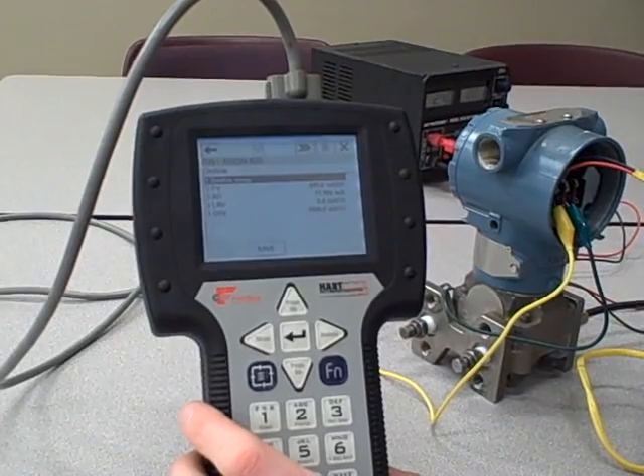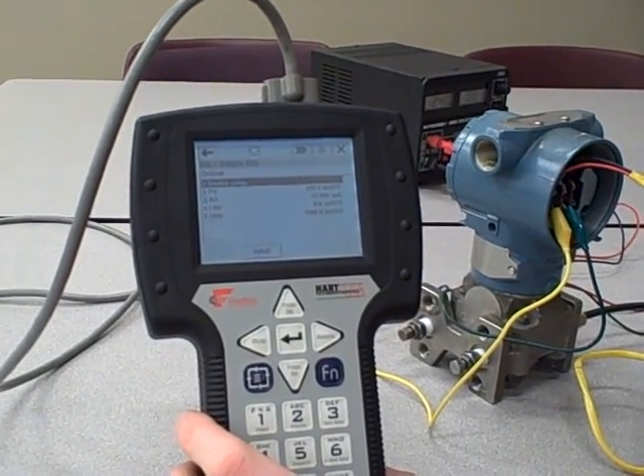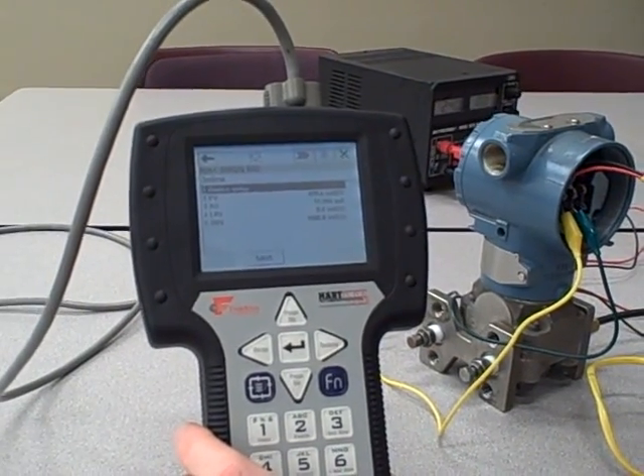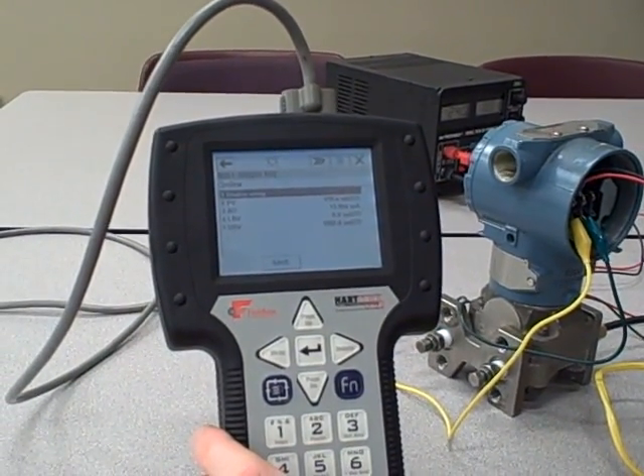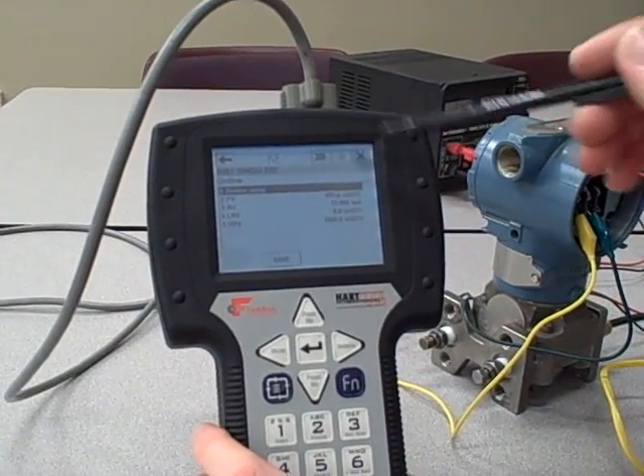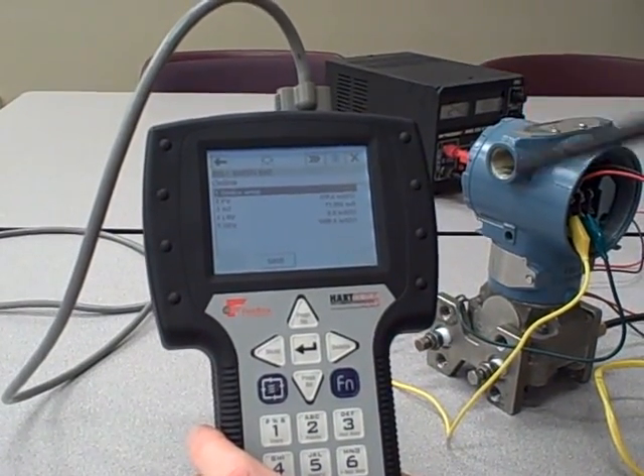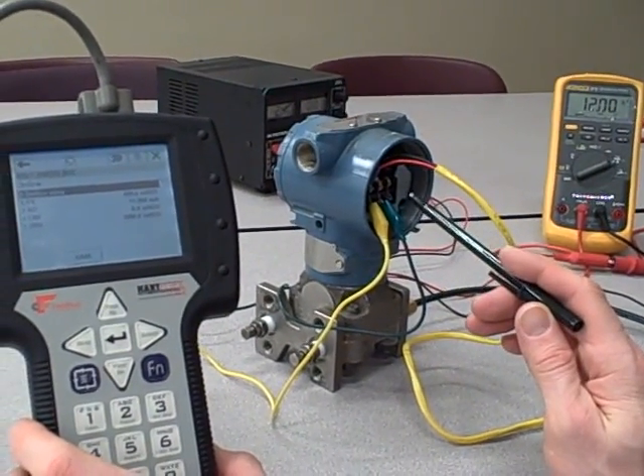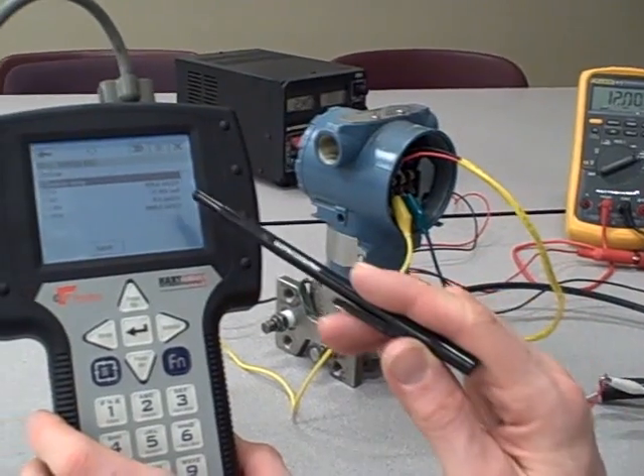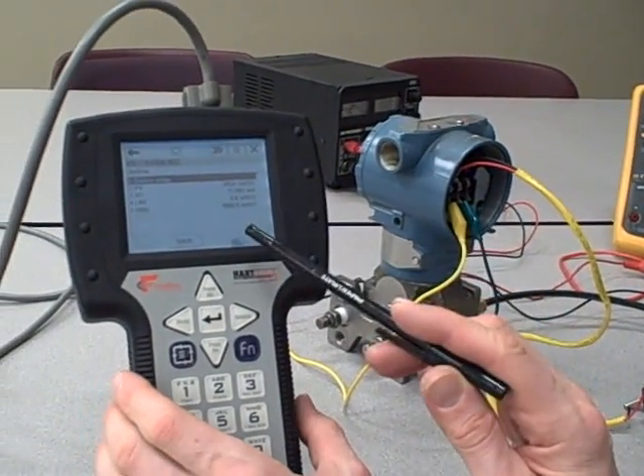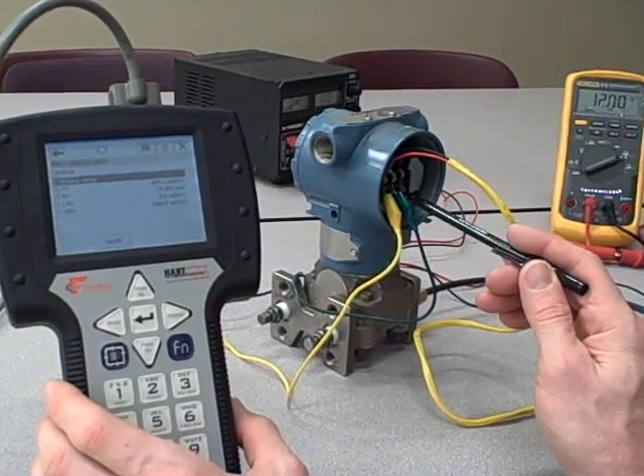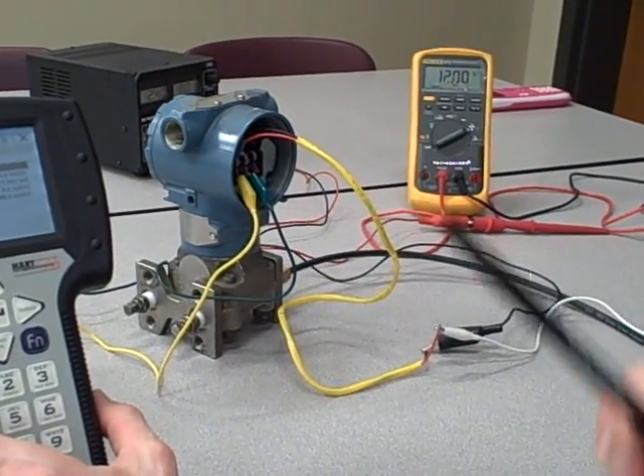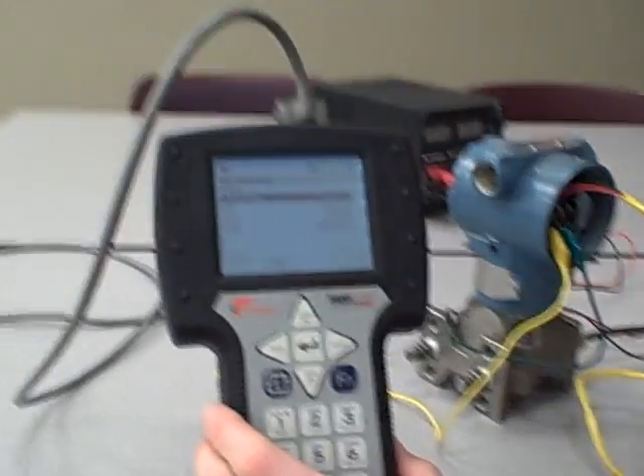So many features, options, and parameters are accessible using one of these HART Communicators. It's a world of options, far beyond what we ever had with old analog-only devices. But remember, this communicates using pulses of AC voltage and current, superimposed on the same two wires that the DC 4 to 20 milliamp signal goes through. I can attach this communicator to the transmitter directly in parallel, or anywhere in parallel along the signal cable leading back to the power source.